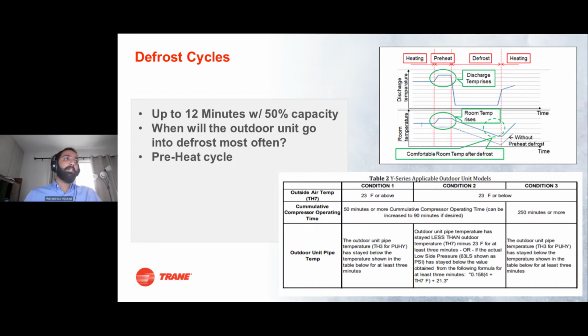The table that's shown at the bottom right hand of the picture is the decision tree for our condensing units on how they decide to go into defrost mode. But broadly speaking, there are three main considerations, which is the ambient temperature, the condensing unit pipe temperature, and the cumulative runtime below 32 degrees. The defrost cycle does last for 12 minutes, but during this, as previously mentioned, you will still have 50% heating capacity during this time.